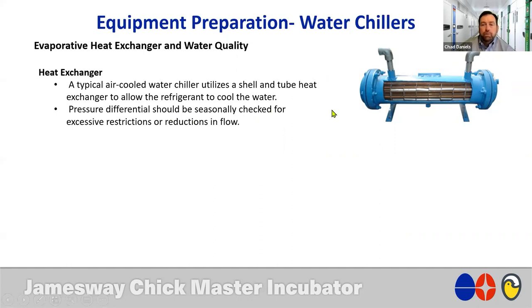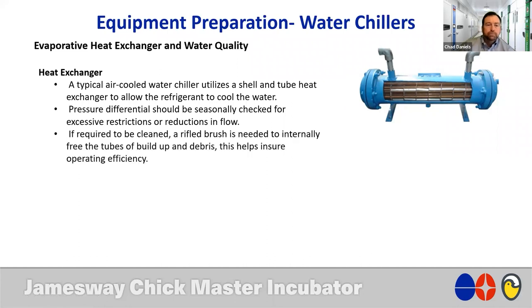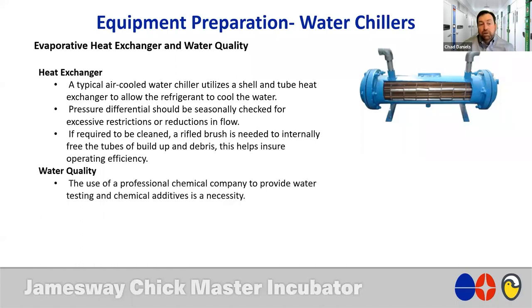And if our pressure drop is too great across that, it's generally an indicator that we have some restrictions and some buildup. If it is required to be cleaned, generally you have to use a rifled brush to run through the tube in order to remove the debris. A lot of times the water quality is unfortunately the contributing factor to if a shell and tube heat exchanger needs to be cleaned. The use of a professional chemical company is generally recommended in order to make sure that our water quality is in good condition. All too often, we find ourselves in hatcheries that are in a region where they don't have to worry about extreme cold. And so therefore, there is no water treatment in some cases.